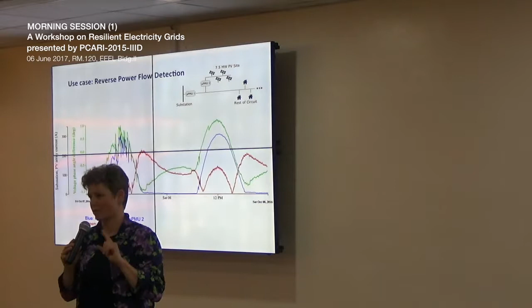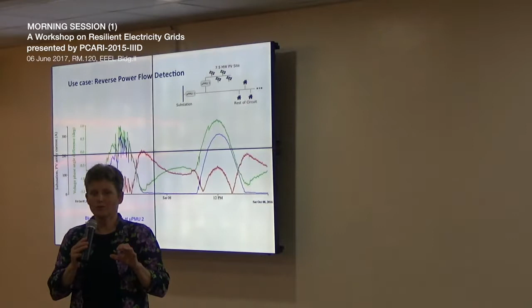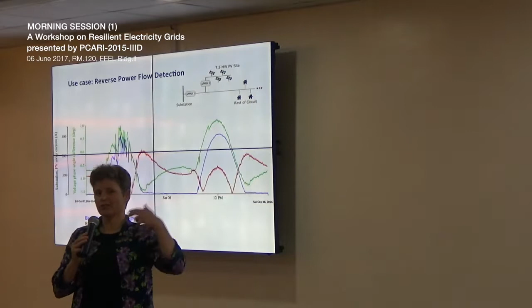You can see how the brown curve is sometimes correlated with the green and sometimes anti-correlated, and sometimes correlated with the blue and sometimes not. Looking at the phase angle difference, it actually crosses zero about the time the current reverses. Interestingly, the current isn't exactly zero when it reverses—this makes a great test question for a power engineering class—because the inverter is producing at about unity power factor, 0.99, while the load is somewhat inductive and draws reactive power. That reactive power is still used by the load even as the real power changes direction, so there's always some non-zero current.